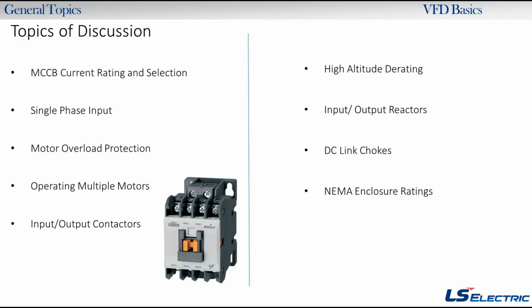Single phase input is a common thing we're asked every day. What does that mean? Can we do single phase? Well, yes, we can, but let's talk about it. Motor overload protection on a VFD, why that matters, why we need to care about it. Operating multiple motors, input-output contactors, high altitude derating, that depends on your area if you get into that. Input-output reactors, DC link chokes or DC reactors, and then lastly we'll talk about some NEMA enclosure ratings.